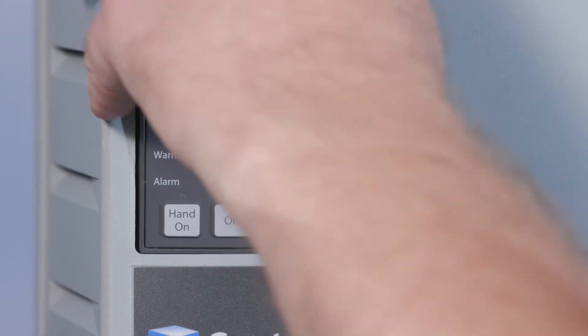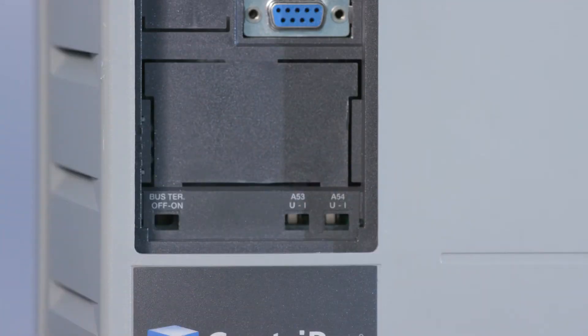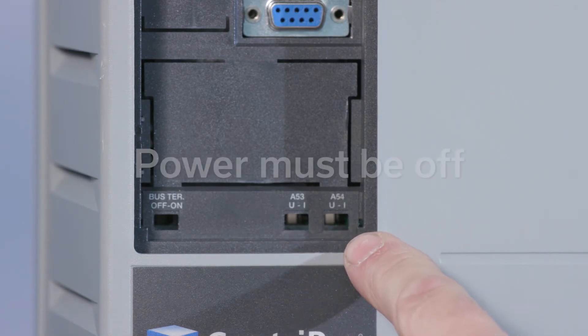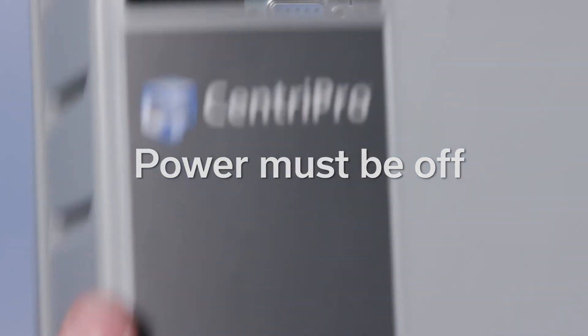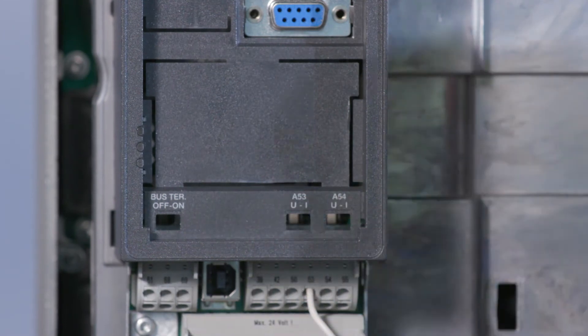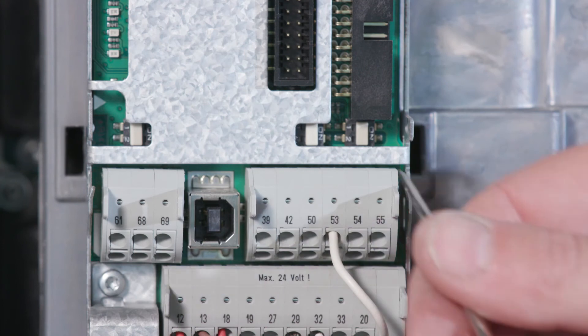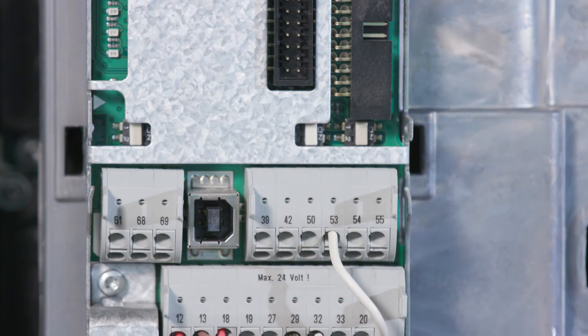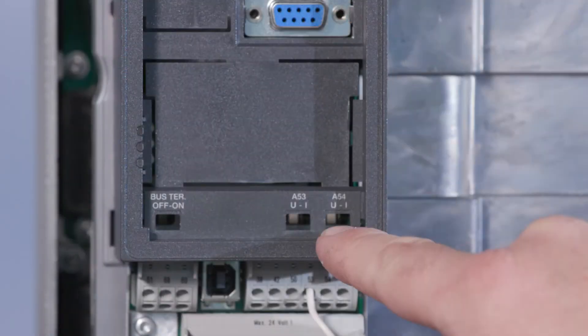The dip switches located behind the LCP must match the corresponding feedback device. When the dip switches need to be changed, the power must be off. For example, when using a 4 to 20 milliamp transducer on analog input 53, the dip switch for A53 must be set to I, which stands for current. When using a 0 to 10 volt DC transducer on analog input 54, the dip switch for A54 must be set to U, which stands for voltage. Note, your IPC may have the dip switch on A53 permanently fixed to I.